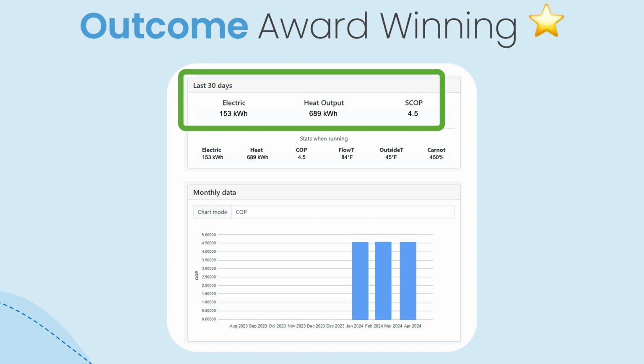Circled in green, it's consumed 153 kilowatt hours and actually generated, in terms of providing heat, 689, which is 4.5 times higher - the coefficient of performance. The average outside temperature has been 45, I think I said 40 earlier, and the average flow temperature has been 84. But it was designed for peak demand at 100 Fahrenheit flow temperature, with outside around 30, I think.